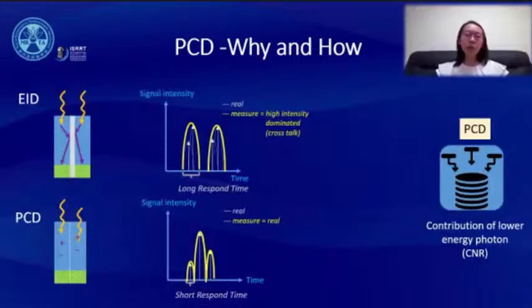The longer response time of the two-step EID also undermines the contribution of the low energy photons. Let's see in the upper image. There are actually 4 photons coming into the detector, but only 2 mixed signals are finally read out, and they are all higher energy weighted. The contribution of the lower energy is not read, and finally the overall energy profile is high energy dominated. On the lower part of this PPT, we can see the shorter response time in PCD helps to settle this problem, as we can see the lower and higher energy photons contribute with the same weight as they are detected one by one by the system.